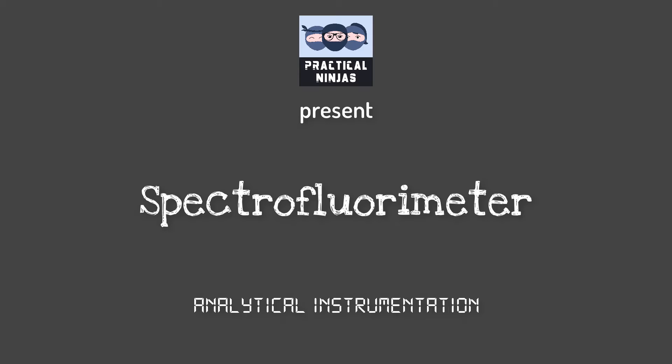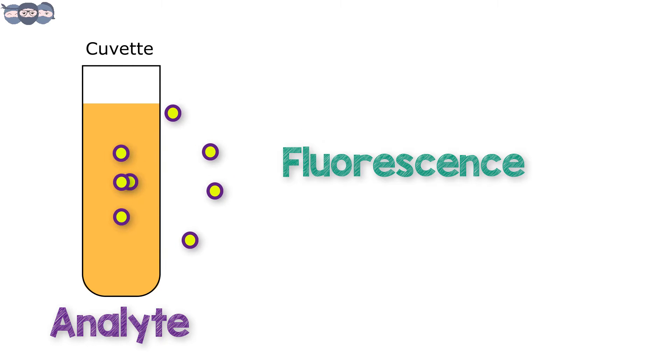Welcome viewers. In this video we will be discussing the spectrofluorimeter, an instrument used to study fluorescence emitted by an analyte. The principle of spectrofluorimeter is that it uses the fluorescence produced by the analyte to perform qualitative and quantitative analysis on it.